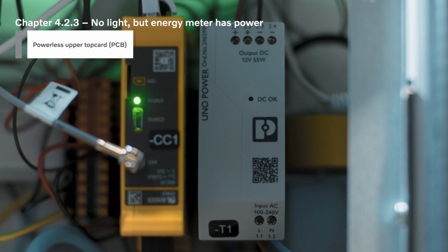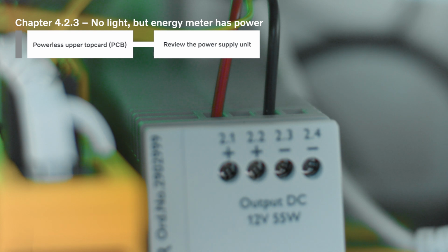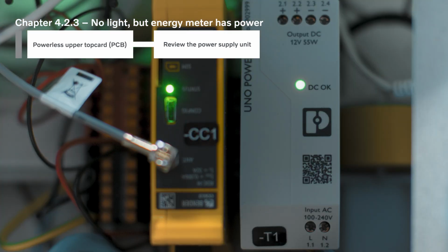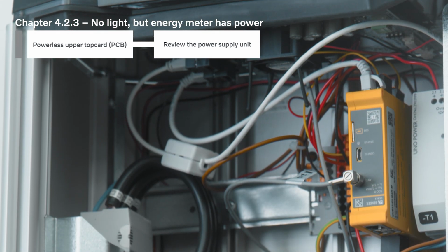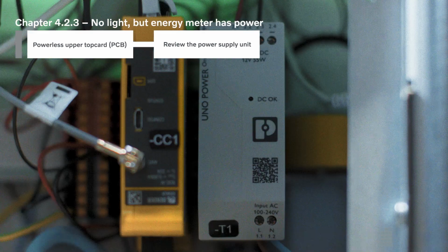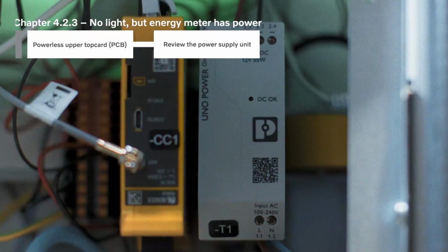If the upper top card doesn't receive power from the 12-volt supply unit, try to disconnect the red cable and the black cable from the 12-volt power supply unit on the terminals plus and minus. If the green light labeled DC OK on the 12-volt supply unit lights up when you disconnect the two cables, this indicates that the 12-volt supply unit has power and that it has detected an earth fault in one of the DC-powered components in the charging station, like for example the controllers, the upper top card, the router, etc. If the green light on the 12-volt supply unit doesn't light up, consider replacing the power supply unit.